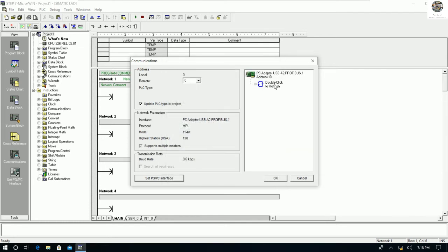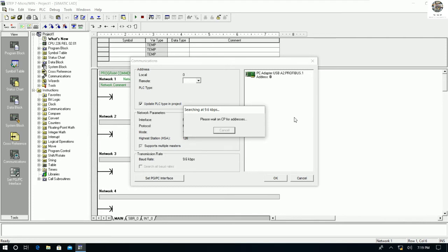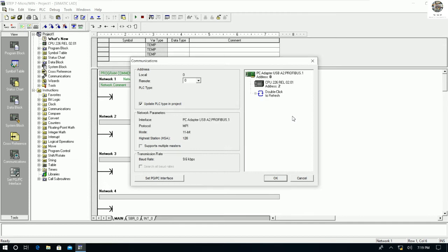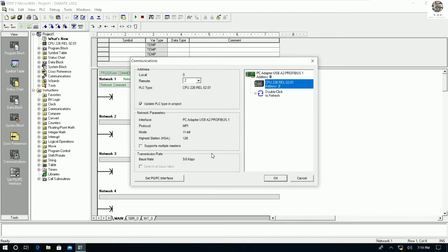Now let's double-click Communication to check again. Wait a moment for communication to establish. We now find one CPU 226 — the CPU of the PLC S7-200 — communicating at 9.6 kbps baud rate. We must follow these steps; otherwise we cannot communicate between our PC and the PLC. Click OK to confirm.